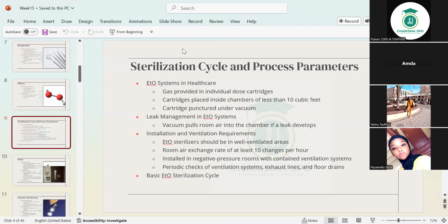And the same thing with these ETO sterilizers. There are gases, so they don't want that gas to be exposed to other people by getting out of that room. The system is made in such a way that when there's a leak, the gas doesn't come out, but rather the leak sucks in air from the room, not letting the air from the ETO system come out. That's why it has the negative pressure. Okay? So we say that it's good to install it in a negative pressure room with contained ventilation systems.